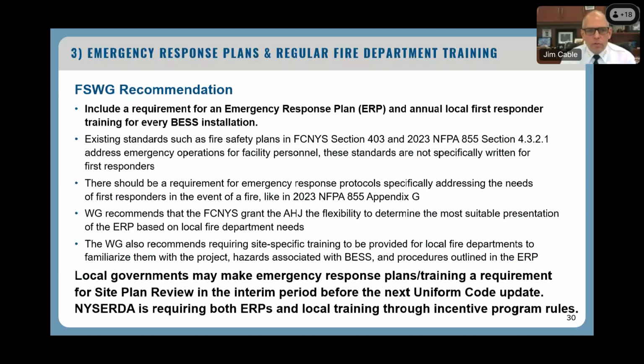A recommendation developed from the working group was to include a requirement for an emergency response plan and also annual local first responder training for every BESS installation or facility. Currently existing standards, including the fire code and NFPA 855, require fire safety plans aimed at facility personnel, but these standards aren't specific to the fire service. So the recommendation was that the requirement should be extended to emergency response protocols specifically for local fire service, should there be a fire or other emergency, like the guidance included in NFPA 855 Appendix G.